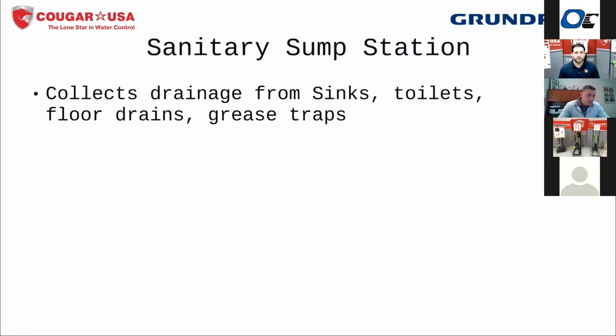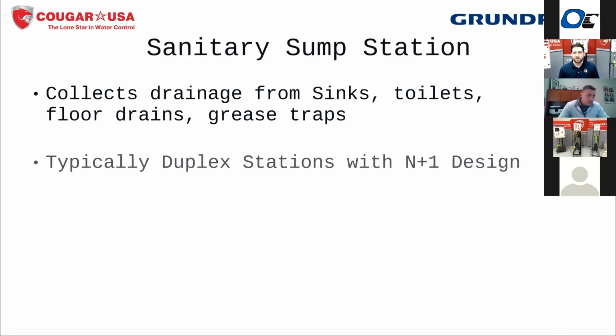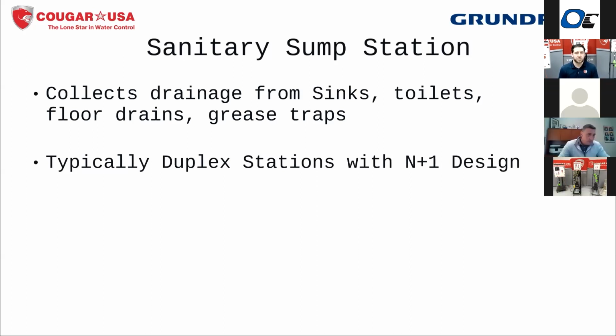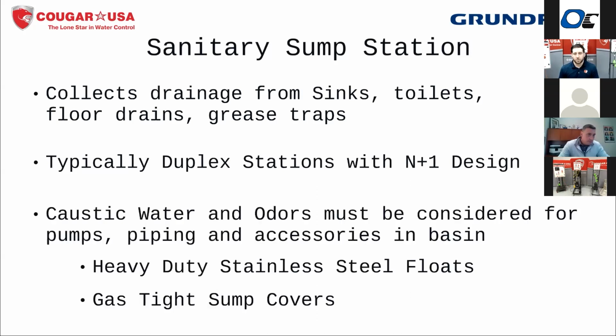Now, if we're looking at the sanitary stations, a little bit different. Anything off of usage here, sinks, toilets, floor drains, et cetera, might be going into these sanitary pits. Grease traps are really something we're going to want to address specifically when we have grease associated with the sanitary sump station. And again, duplex with the N+1 design, but here we don't want to see both pumps run. We really want to be able to have a single pump run and carry a sanitary lift station.